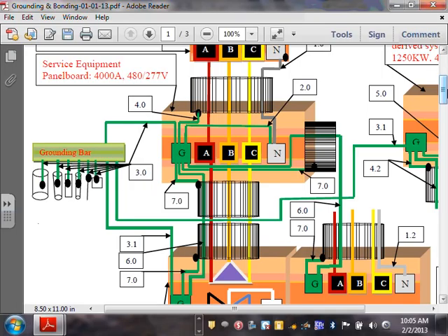What do you need to do with all these conduits? Bond them. You need to bond them. So that number 4, can you guys see that little thing here? This is the so-called supply side bonding jumper. In the past, before 2011, there used to be an equipment bonding jumper on the line side of the service disconnecting means. Now remember, my service disconnecting means is sitting right here. I'm not showing the service disconnecting means. So number 4 is what we call a supply side bonding jumper. You guys are familiar with supply side bonding jumper? Okay.